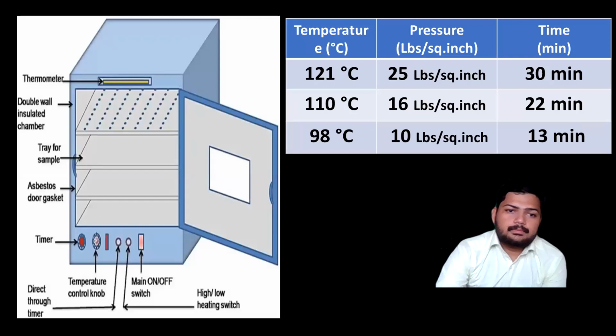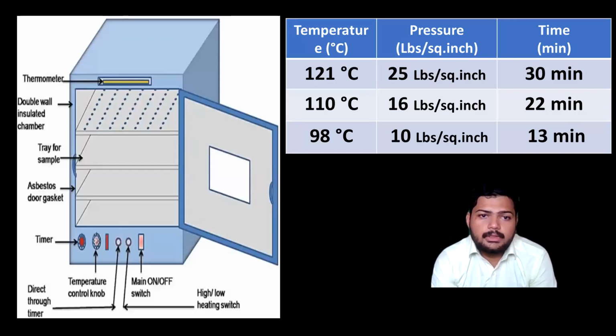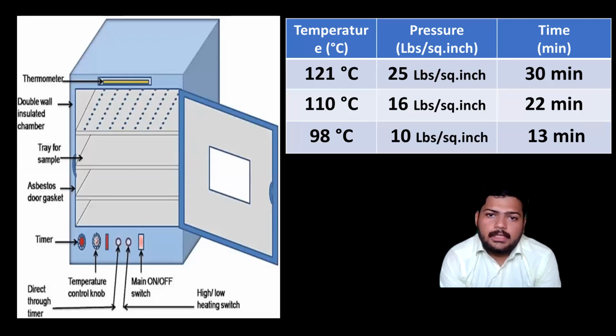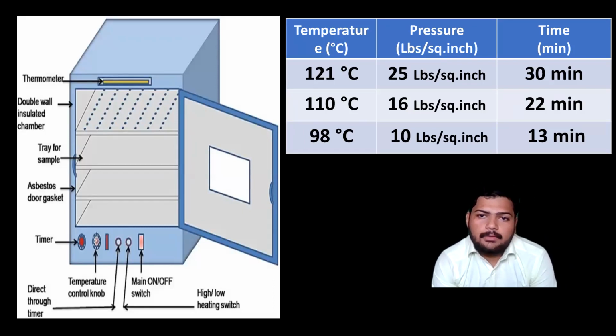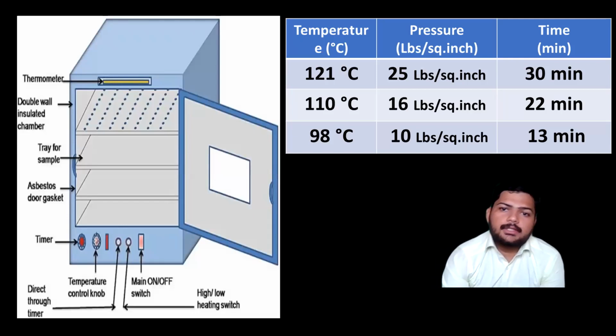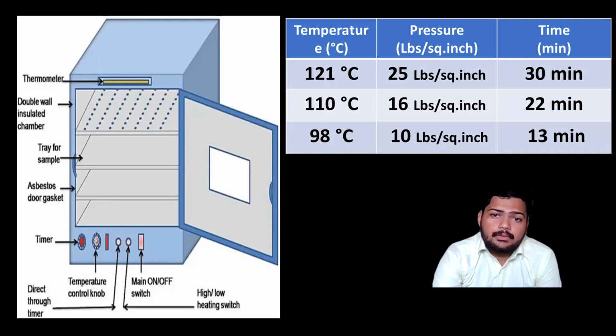Next, we will see the structure. It contains a thermometer to read the temperature, a double wall insulated chamber, a tray to place the sample in, an asbestos door gasket, a timer, a temperature control knob, a main on off switch, and a high low heating switch. We are going to take three readings for the same: 121 degrees Celsius for 30 minutes at 25 lbs pressure, 110 degrees Celsius for 22 minutes at 16 lbs pressure, and 98 degrees Celsius for 13 minutes at 10 lbs pressure. The readings can vary as per the experiment.